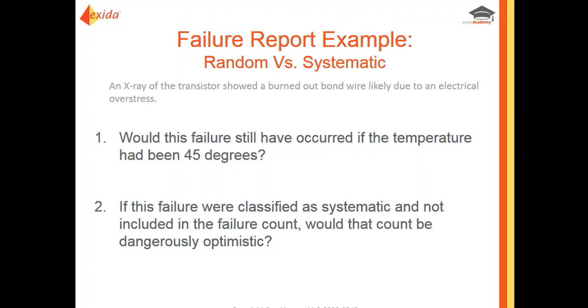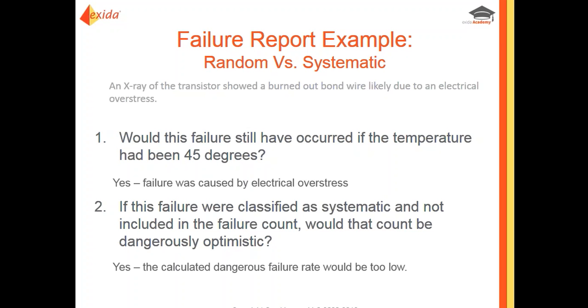The big clue was: an x-ray of the transistor showed a burned-out bond wire likely due to electrical overstress. The first question to ask is: would this failure still have occurred if the temperature was 45 degrees instead of 55 that day? Well, yes — the failure was caused by electrical overstress. So if this failure were classified as systematic and excluded from the failure count, the calculated dangerous failure rate would be too low.